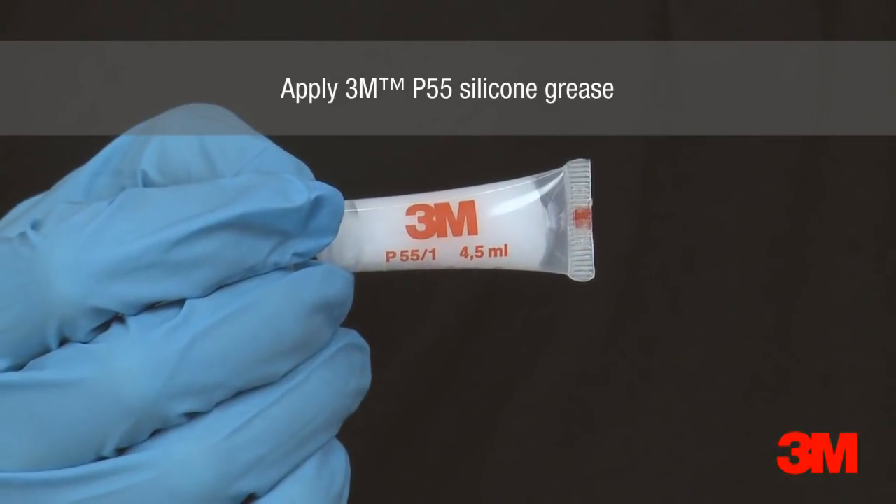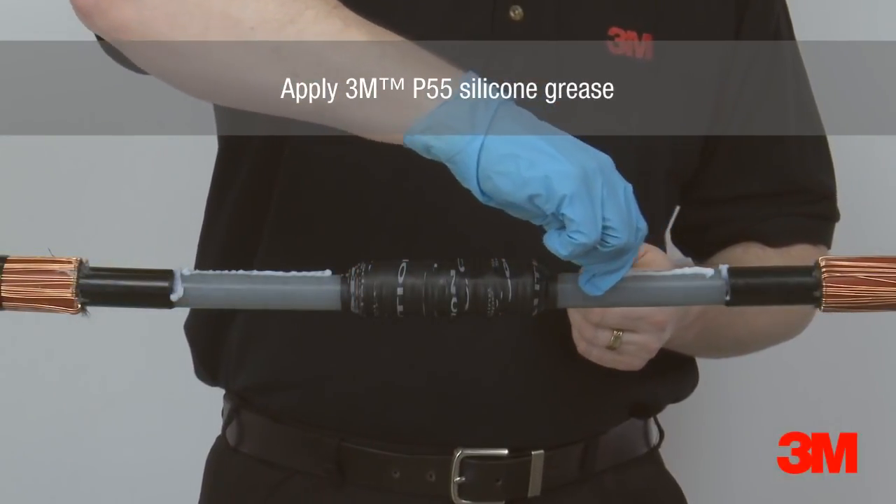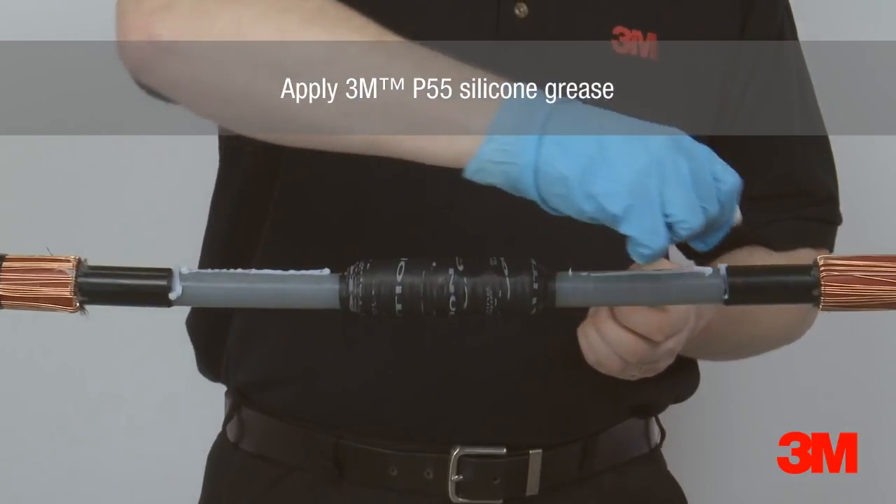P55 silicone grease is applied over the primary insulation, semiconductor screen and connector, remembering to leave the connector to last to avoid contamination.